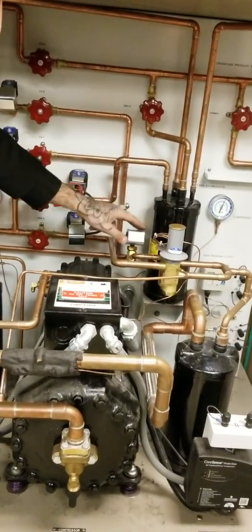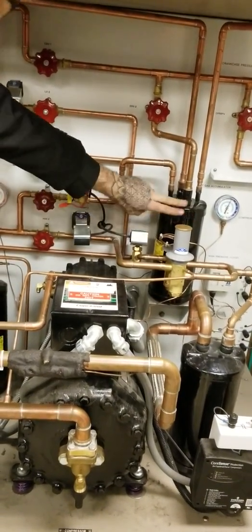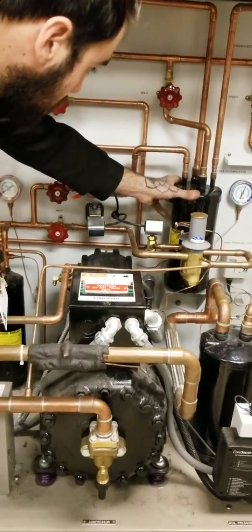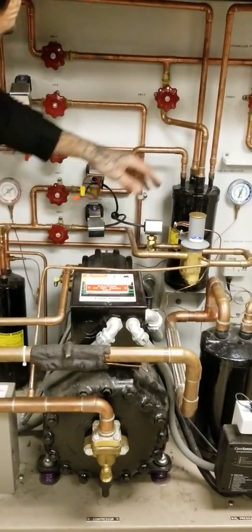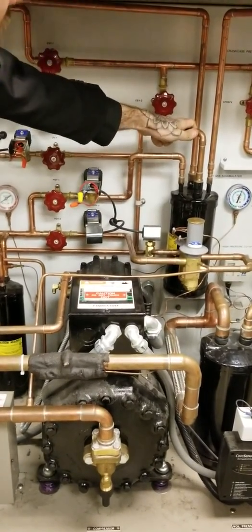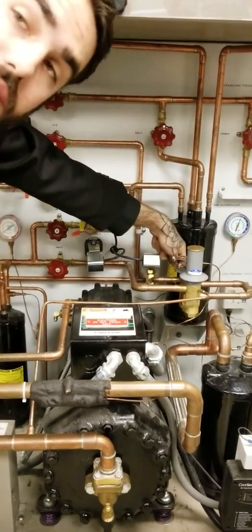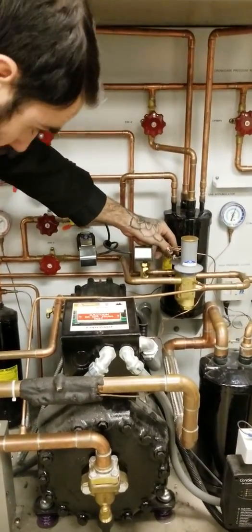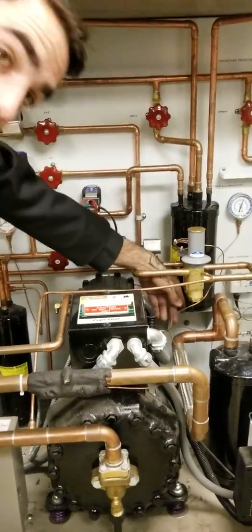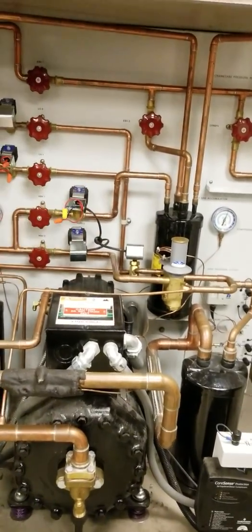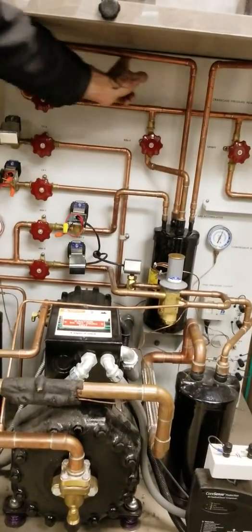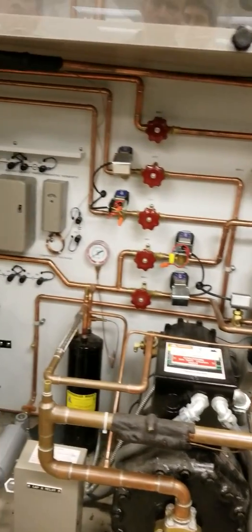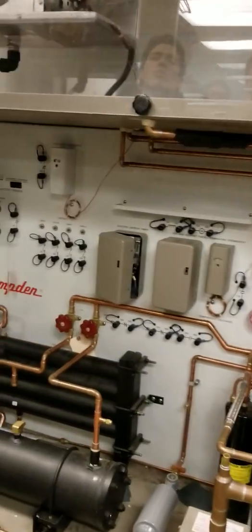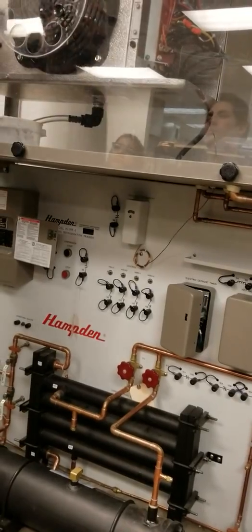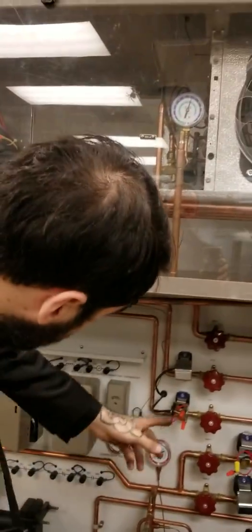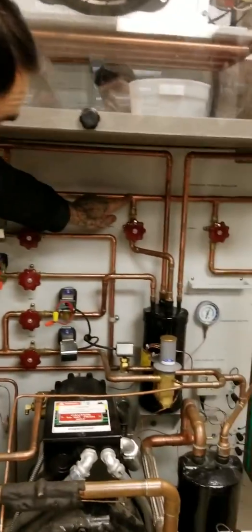So our subcooled refrigerant is going to fill up this drum. In this drum we have this line, which is a straw that comes all the way back down, similar to the oil receiver, so that it only gathers liquid refrigerant, sucking it off the bottom, and it delivers that to your typical metering device. In this application we have TXVs, so it tees off, right? It comes up and tees off.